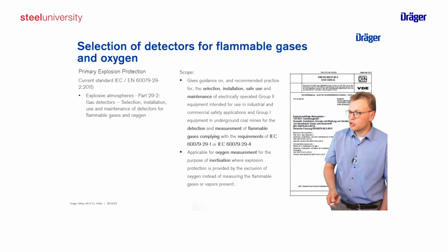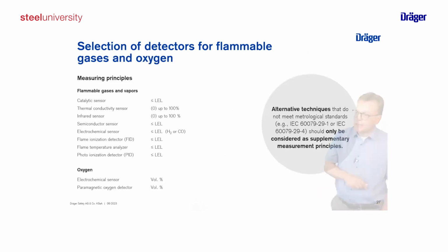We come in the next chapter to this performance. What kind of technologies and sensors can we use based on these standards? We concentrate on the flammable gases here, so we always try to be below the explosion limit. There are catalytic bead sensors, infrared, semiconductor, electrochemical, FID, PID. These are typical sensors which can be used for flammable gases. But if we want to detect hydrogen, and we come later to the sensors themselves, we can mostly concentrate on only two sensor technologies: catalytic sensors and electrochemical sensors.